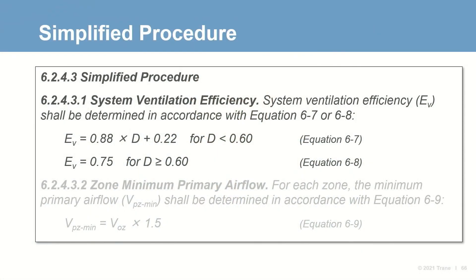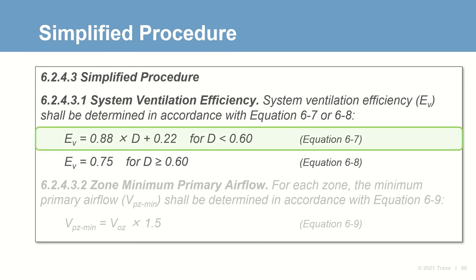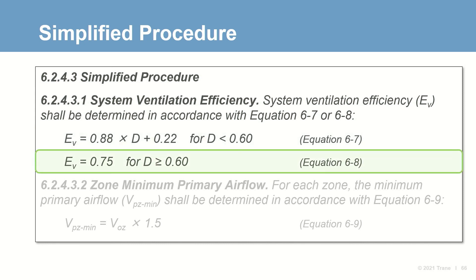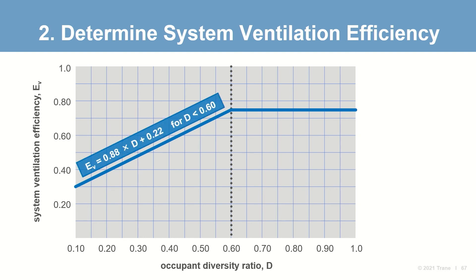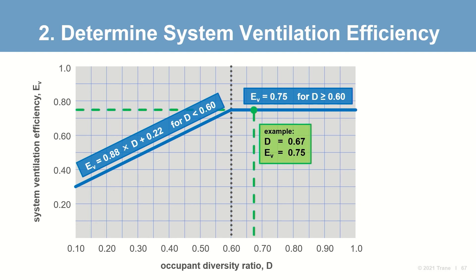When using the new simplified procedure, system ventilation efficiency is simply a function of the Occupant Diversity Ratio D. If D is less than 0.6, E-sub-V is calculated using a specific equation. If D is greater than or equal to 0.6, then E-sub-V equals 0.75. In our example, D is 0.67, so System Ventilation Efficiency is 0.75.